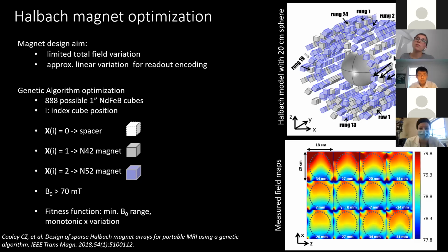The resulting magnet design is shown on the upper right. You can see the distribution of the two different neodymium magnet grades. On the bottom is the measured field map, and the oval outline is roughly the size of a brain in the field of view. You can see that our field is about 79 millitesla, and we have this variation across the X direction that we want to use for the image encoding.